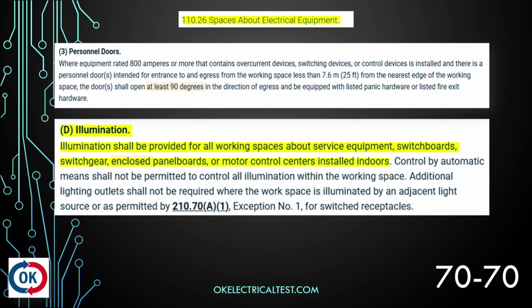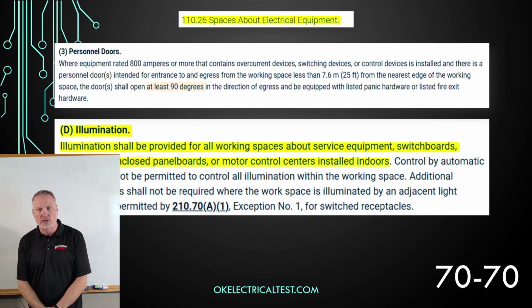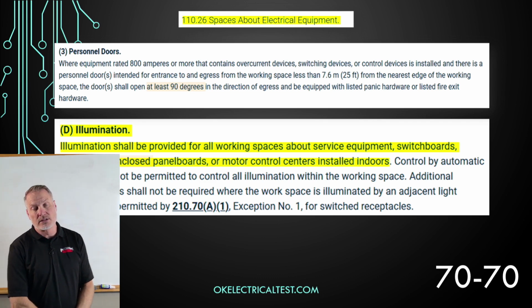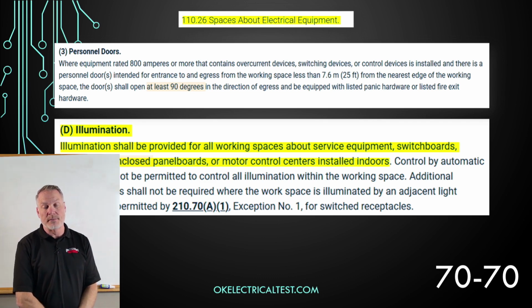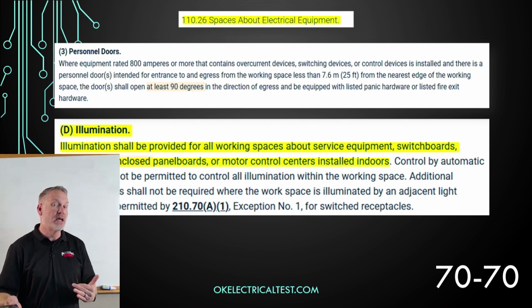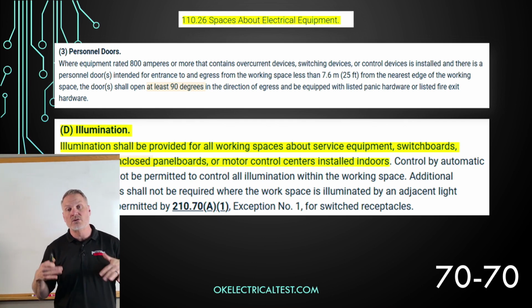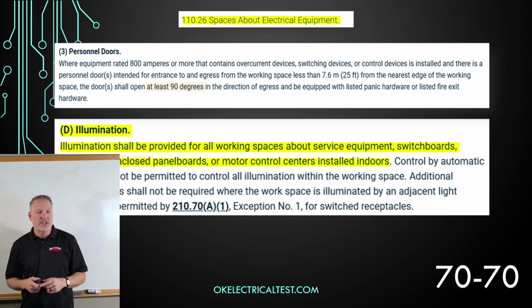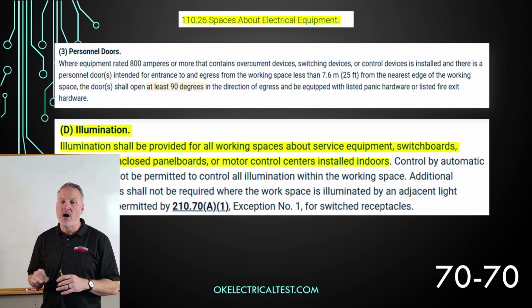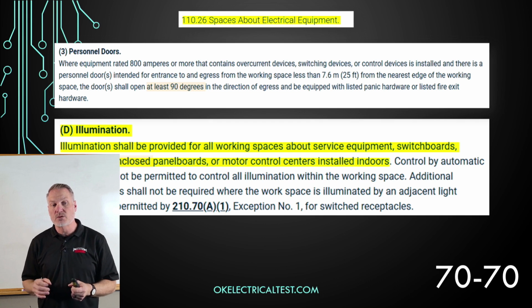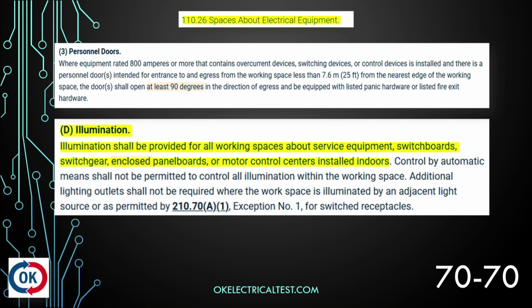Let's move to letter D. Still under 110.26, spaces about electrical equipment. We've got letter D, illumination. So this is the illumination of that electrical equipment. And again, in context, specifically electrical equipment, 1,000 volts or less. Letter D, illumination. Illumination shall be provided for all working spaces about service equipment, switchboard, switchgear, enclosed panel boards, or motor control centers installed indoors. Control by automatic means shall not be permitted. All right, so basically, if I've got electrical equipment, I got to be able to see it to service it, right? And so we need to have illumination of some sort in there.